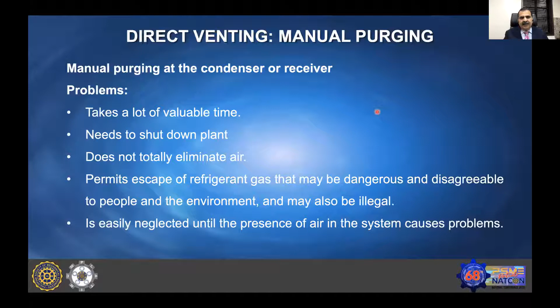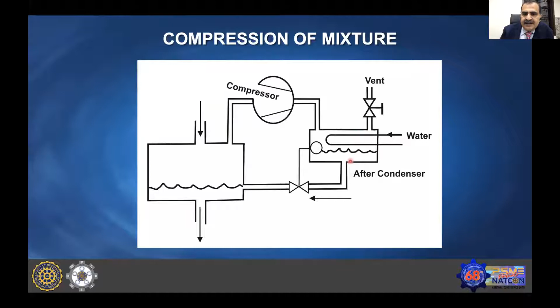Another method is purging by compression, in which a compressor and a condensing unit are made with a different refrigerant. Gas is taken from the receiver, compressed and brought to the condenser side. Whenever the ammonia gets condensed, the non-condensable gases are vented out, and the condensed liquid is brought back into the receiver.